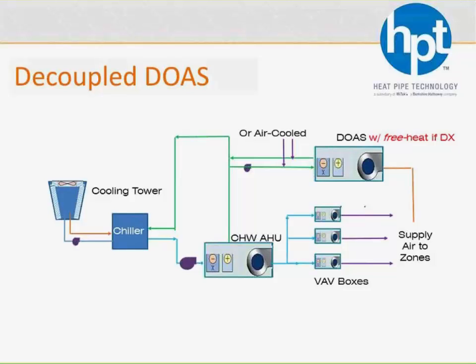Now, whether we're talking DX or chilled water, air-cooled, water-cooled, it could be anything serving that DOAS unit, or even the recirculation units. They're each doing their own thing. The recirculation is focused solely on sensible load. There is obviously some humidity and some moisture in the return air, but it's minimal compared to all the sensible heat that's coming back. So the recirculation units are just worried about the temperature, while the DOAS unit is worried about ventilation and humidity control. And if it is a DX unit, then you get the benefit of free hot gas reheat. So now that whole half COP hot water loop, or even worse, electric heat, a lot of that gets eliminated because you can get free hot gas right from the DOAS unit.